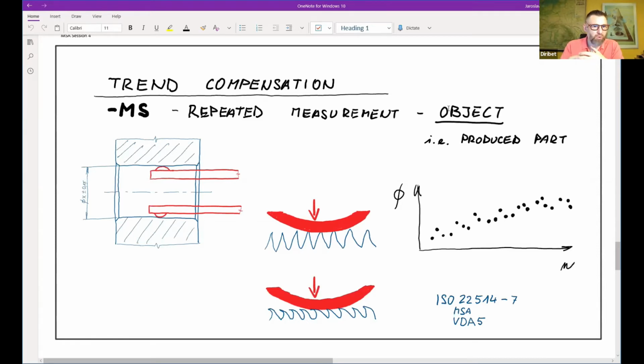Many times we may have good motivation to measure the object rather than the reference in the MSA experiment, notably when we don't have the references, or not enough of them to measure the linearity. For the linearity, as we talked about last time, we should have at least 5 specimens of different sizes, and this is not really easy to do with references. So that will be the primary motivation.